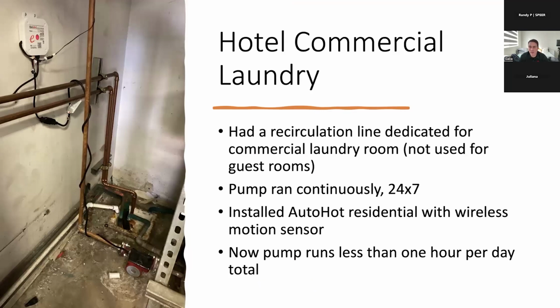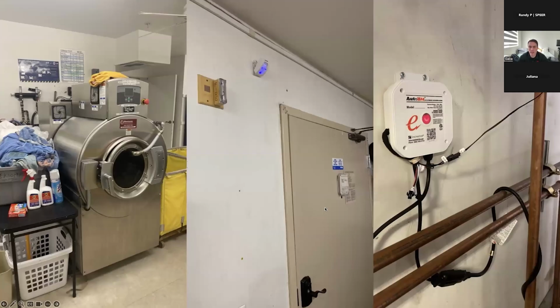So here's an example of a commercial application where we saw there was a circulation pump that was circulating the hot water from the main boiler room to a commercial laundry room, and it just ran 24/7. So this was not the circulation pump that was serving all of the rooms. It was just for this one area. And so we thought, this is a very easy pump to control. So we just installed the control that has a little temperature sensor on the return line. And then we hooked up, if you can see this middle picture here, a little wireless motion sensor, so that anytime somebody was in the room actually doing laundry, that's then and only then was the pump turning on. And then it was only running for a minute or two until the return line got satisfied, and then it shut off. So instead of running 24/7, now it's only seeing about 10 minutes of runtime per day.